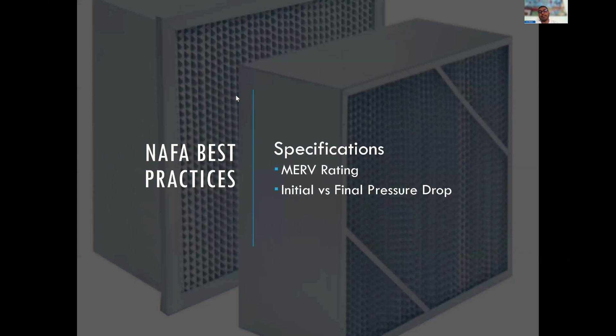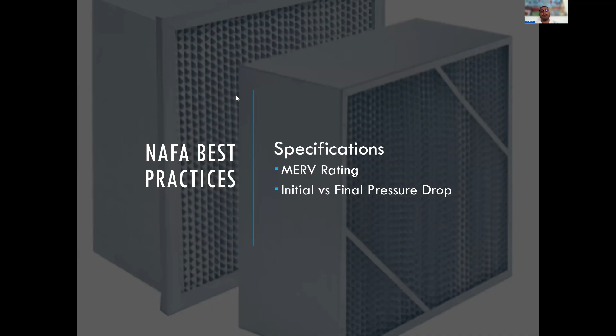From a specification perspective, it gets a little bit more interesting because now we're talking MERV rating. Long story short, years ago, we all know it was MERV 8 filters that were the thing. Went up to MERV 13, now MERV 14, in some cases, MERV 15, 16. It's very difficult to sit in one place and say that there is a standard application for every piece of equipment for every data center. However, if you use the resources that you have available to you, getting information from the right engineers, suppliers, getting feedback from the manufacturers, you'll stand a greater chance in choosing the right product for your application.